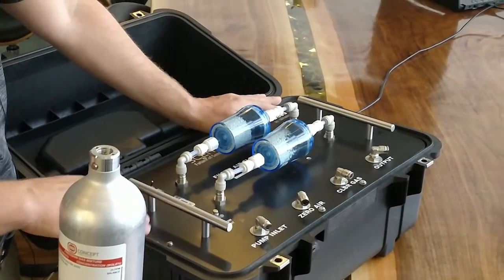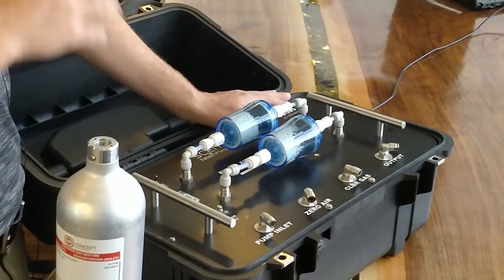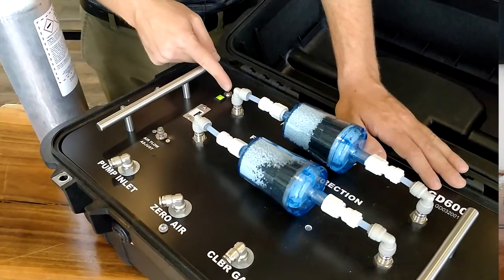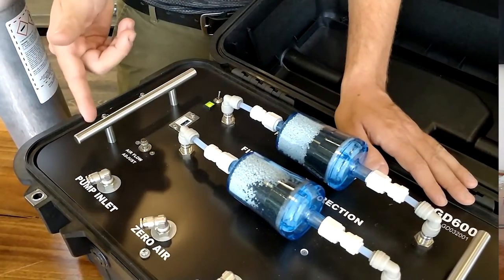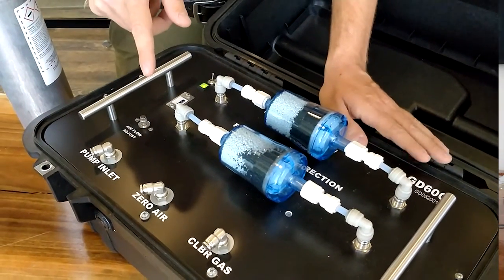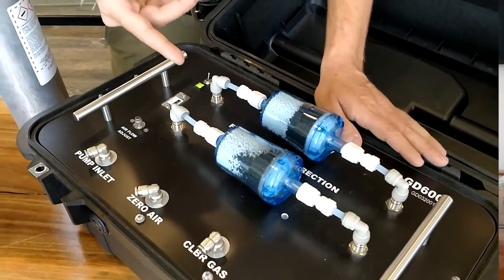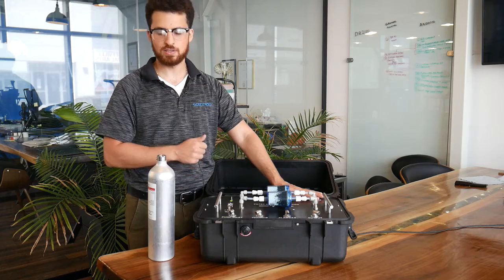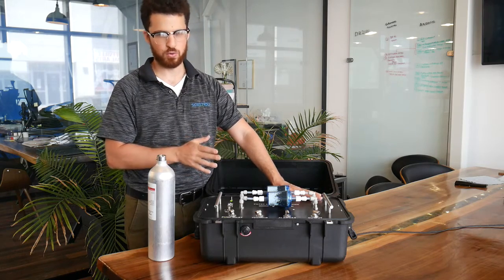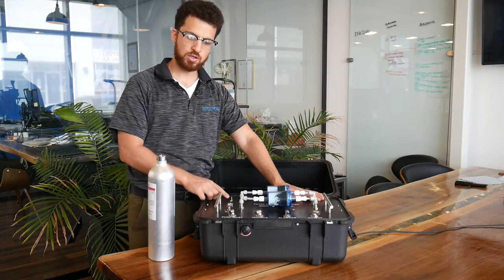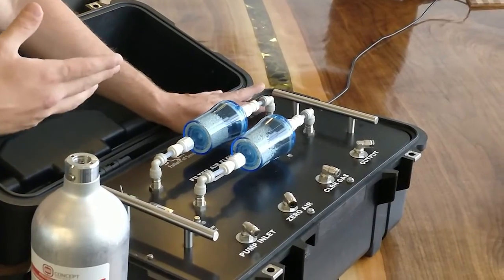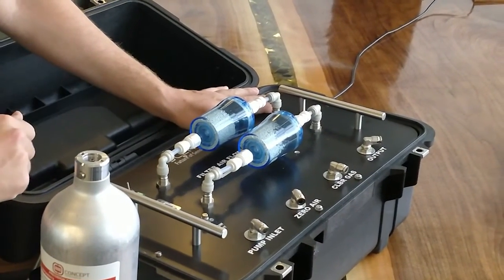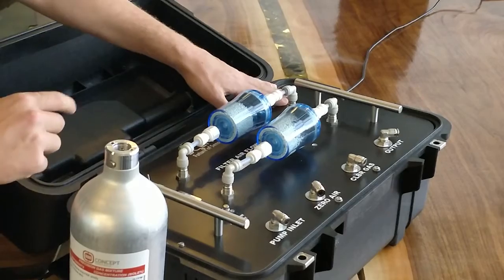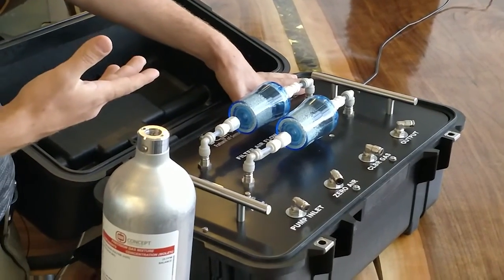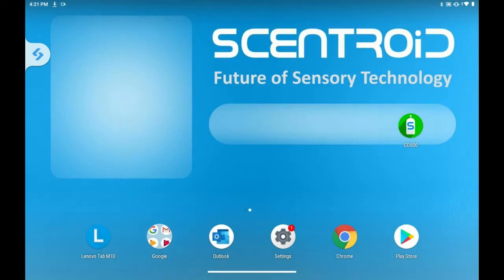released. So to start up the GD600, you would first turn it on. The first thing you should check is to make sure that the LED is green, indicating the unit has power. If it isn't, we recommend connecting it to the charger and leaving it for a few hours before using the unit. So once it's on, you would go into your tablet and open up the GD600 app. Once the app is loaded up, you would need to connect to the Bluetooth of the app.